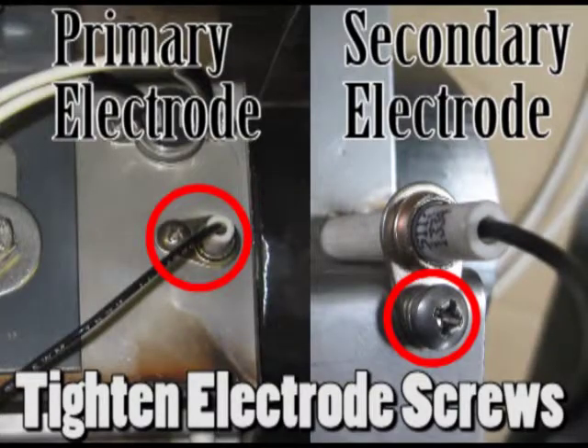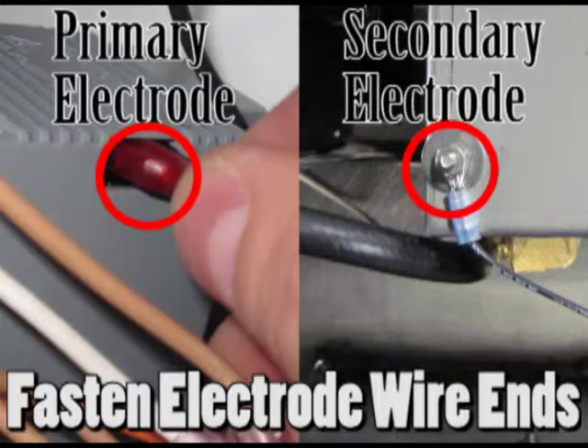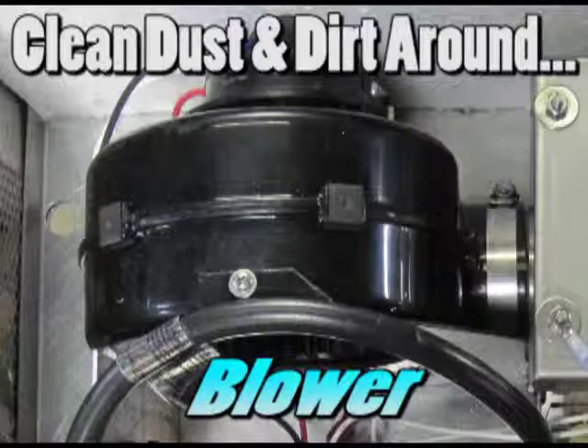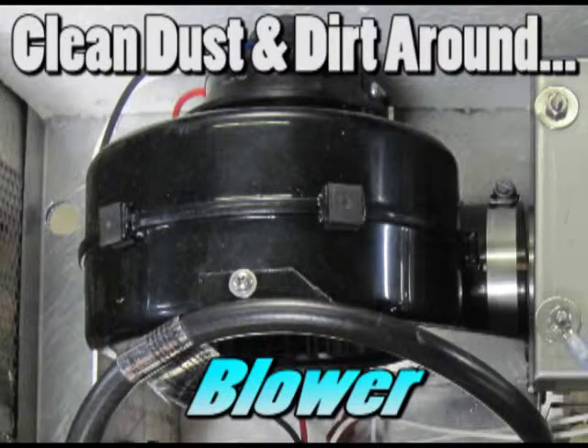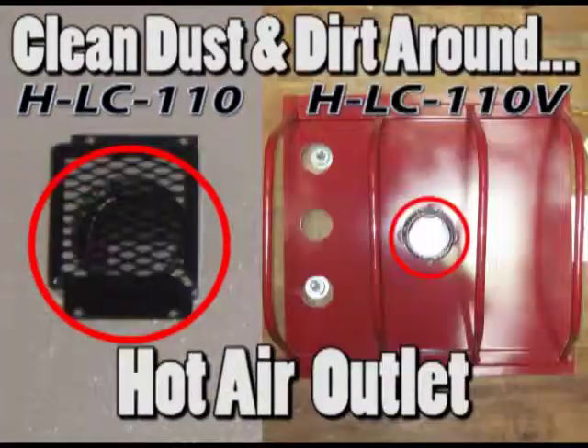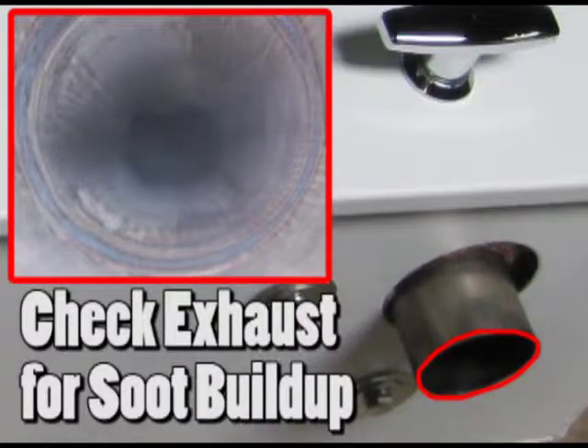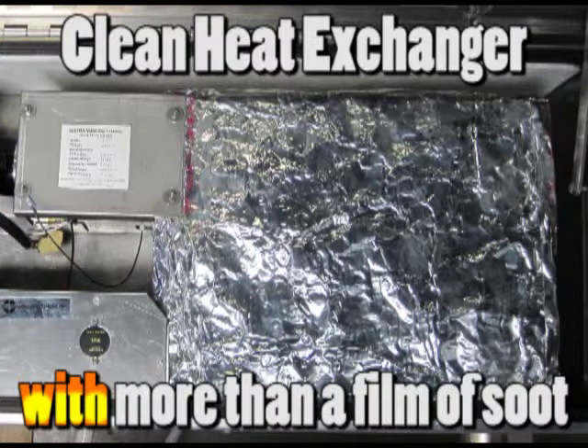Check that the screws for the spark electrodes are tight and that the wires to the spark probes are securely attached. Clean any dust or dirt from around the blower and the air inlets and outlets. Check the exhaust outlet for carbon deposit and clean the heat exchanger if significant deposits more than a film are present.